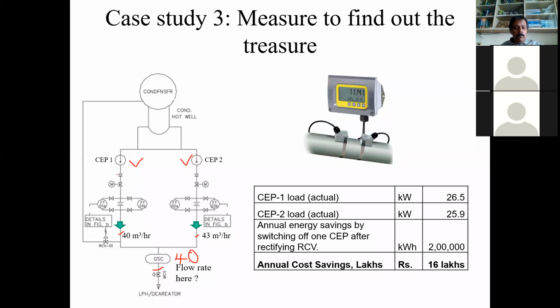Then you go for tracing. What has happened? Where is this excess flow going? And there's a maze of pipelines. In this figure, it is very obvious. There is a recirculation valve here, back to the hot well. This recirculation valve is normally closed, but it was passing, and part of the flow was going through the recirculation valve back to the hot well.